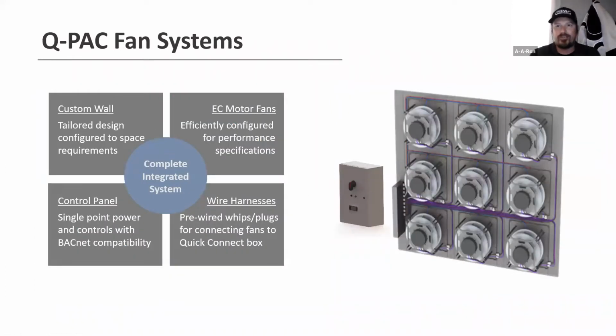And when we talk about the Q-PAC system, it is a complete integrated system. We supply the bulkhead, the EC fan motors, the control panel, as well as the quick connect box, which is inside, that distributes all the power and communication. We supply all the wiring harnesses, hardware, mounting kits. So the only thing that we don't supply in our scope for the system is the power control from the building to the disconnect, and the power control from that disconnect to the interior quick connect boxes. Since we don't know where you're going to mount the disconnects, we don't supply those, but it does allow for a shorter time for electricians to do their wiring process.